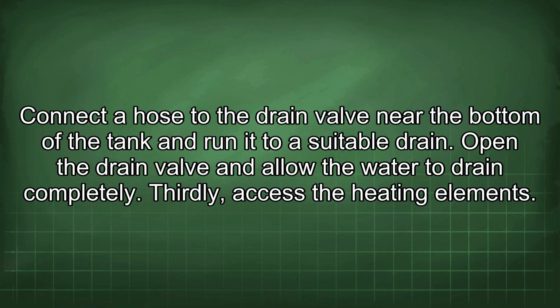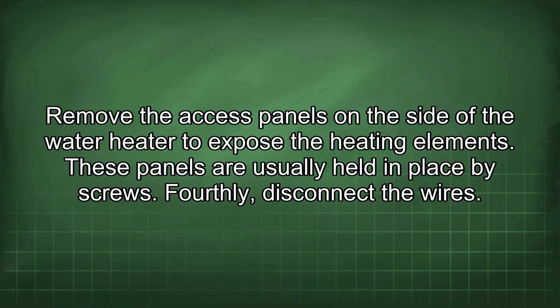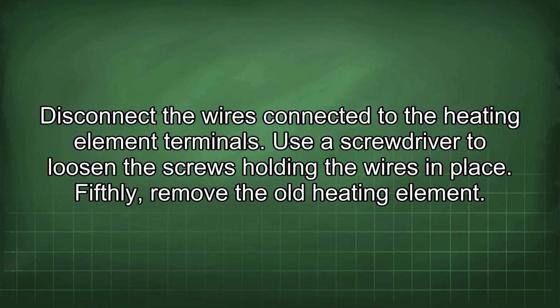Thirdly, access the heating elements. Remove the access panels on the side of the water heater to expose the heating elements. These panels are usually held in place by screws. Fourthly, disconnect the wires. Disconnect the wires connected to the heating element terminals. Use a screwdriver to loosen the screws holding the wires in place.